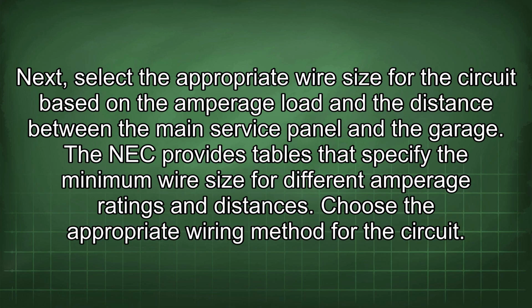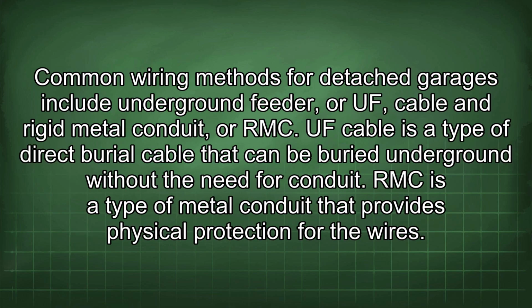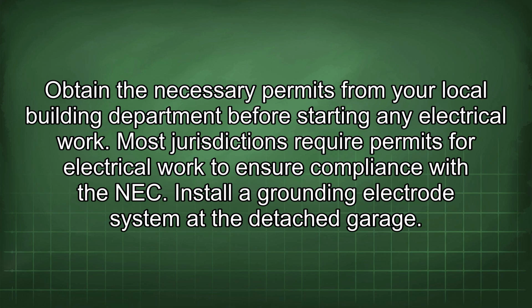Choose the appropriate wiring method for the circuit. Common wiring methods for detached garages include underground feeder, or UF cable, and rigid metal conduit, or RMC. UF cable is a type of direct burial cable that can be buried underground without the need for conduit. RMC is a type of metal conduit that provides physical protection for the wires. Obtain the necessary permits from your local building department before starting any electrical work. Most jurisdictions require permits for electrical work to ensure compliance with the NEC.